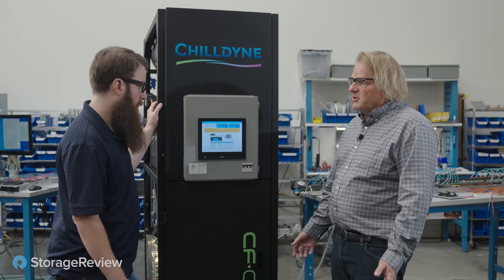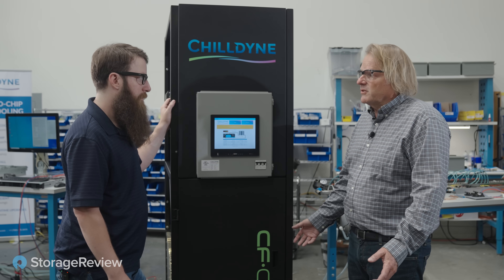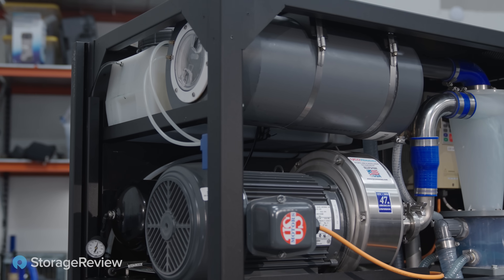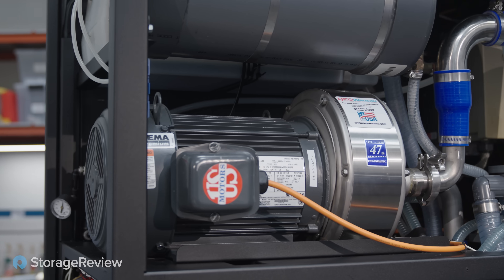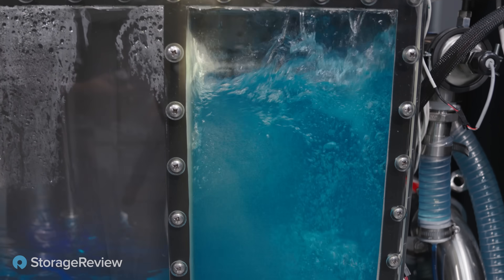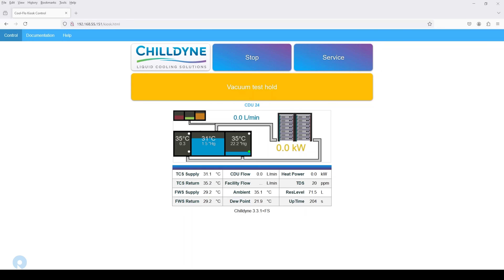In a positive pressure system, you'd have to pressurize the system and wait a little while to make sure it held pressure. With the Chilldyne system, the leak test operation is automated. The first thing that happens is the CDU pulls a vacuum on the system — about 22 inches of mercury — and then shuts a valve. It holds for a second and makes sure the vacuum doesn't fall, confirming no major leaks. And it passed.